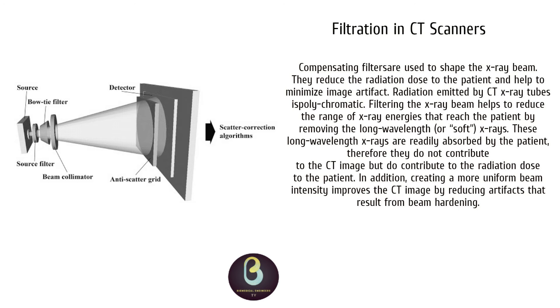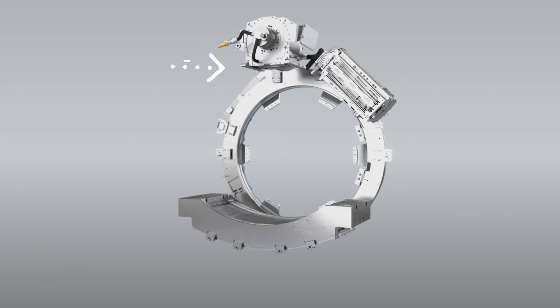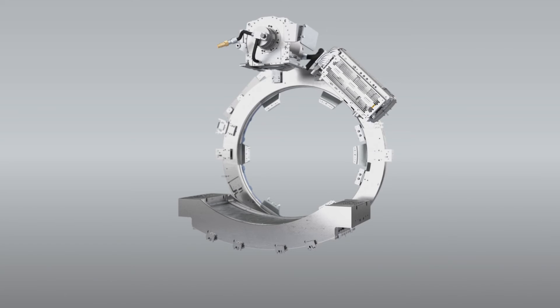The sixth component is filtration. Compensating filters are used to shape the X-ray beam, reduce radiation dose to the patient, and help minimize image artifacts. Radiation emitted by a CT scan X-ray tube is polychromatic. Filtering the beam helps reduce the range of X-ray energies reaching the patient by removing long-wavelength or soft X-rays, which are readily absorbed by the patient and do not contribute to the CT image but do contribute to radiation dose. Creating a more uniform beam intensity also improves the CT image by reducing artifacts from beam hardening.